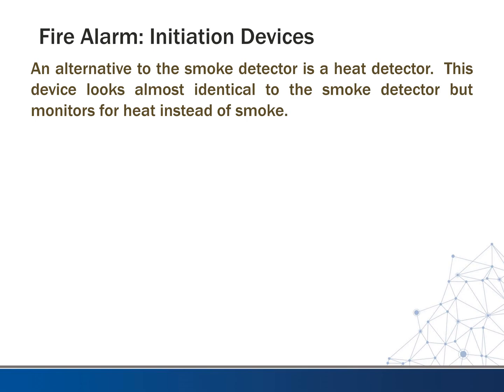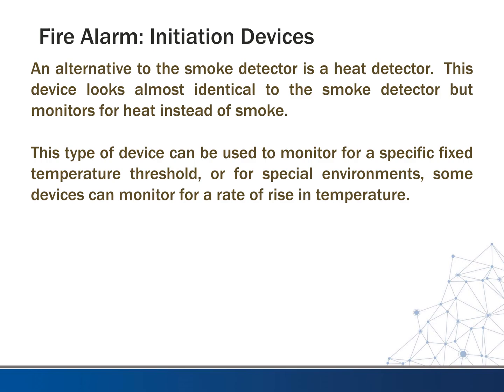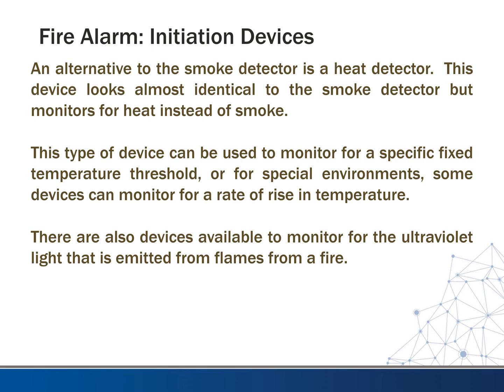An alternate to a smoke detector is a heat detector, which looks almost identical but monitors for heat instead of smoke. This device can monitor for specific fixed temperature thresholds, or for a rate of rise in temperature — for example, if the temperature goes up 20 degrees within five minutes, there's probably a problem. Heat detectors are used in kitchens where cooking produces smoke, and in closets or maintenance rooms where dirt could cause false alarms on a smoke detector.